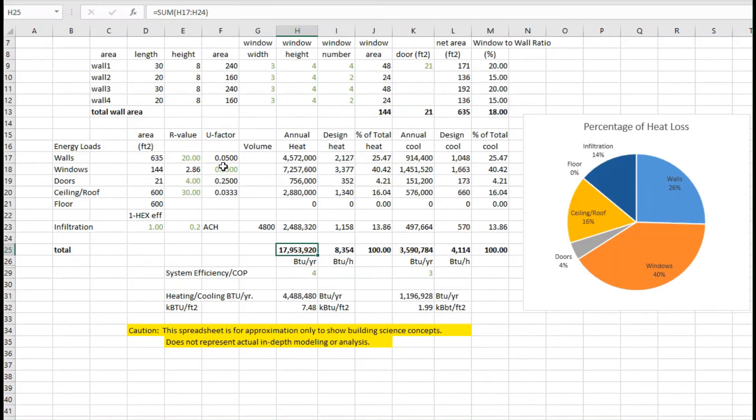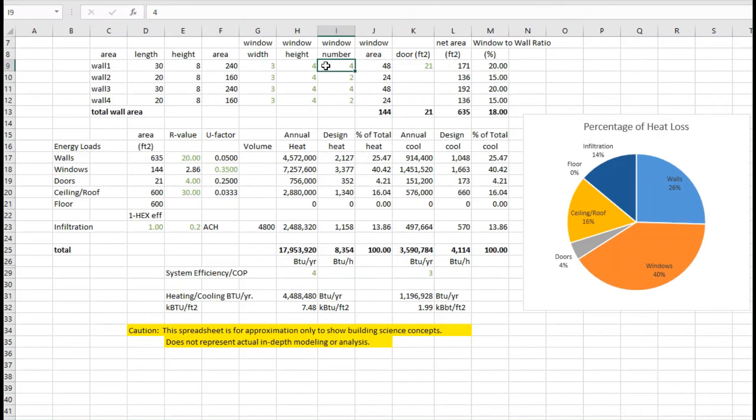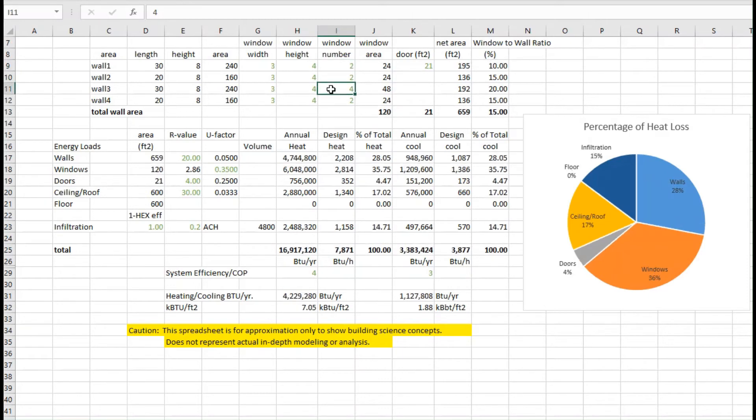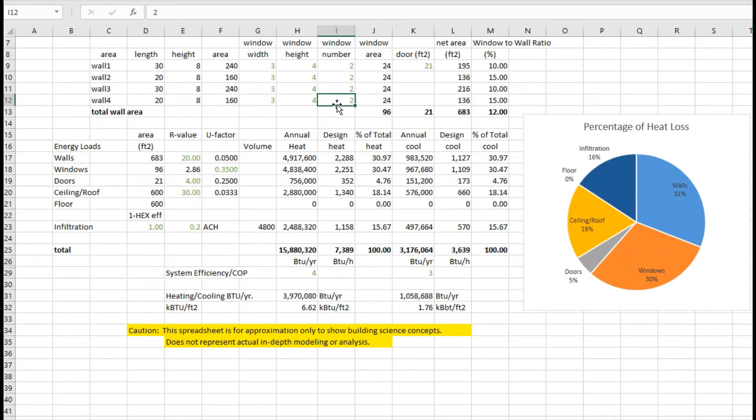The first one - we've got these windows, and so one of the questions is, do you actually need that many windows? Because as you decrease the number of windows, it has a pretty substantial impact. We went from 4.5 down to 3.9. That was almost a 10% reduction by getting rid of a couple of windows on the space.